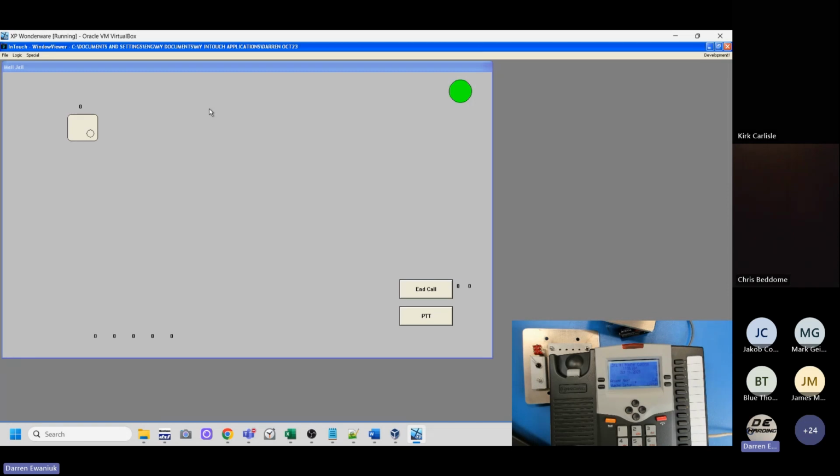The fault bit is bit 7, which is value 128. So if I disconnect the intercom, you'll see it go to 128. It knows that the intercom has a wiring fault on it. We can use that a little later. So that's what happens when you have a call in: you press the call request, you answer the call, and you'll see those values change. Now we can use those.